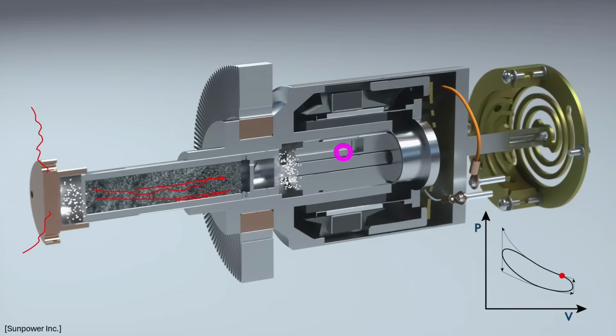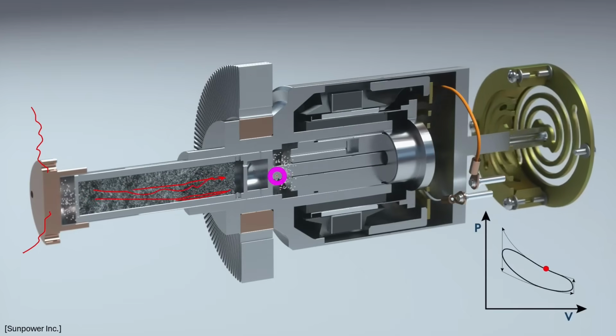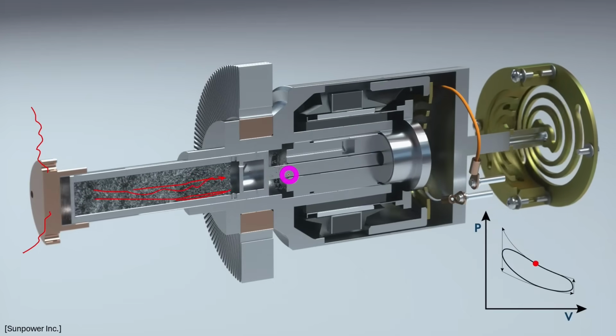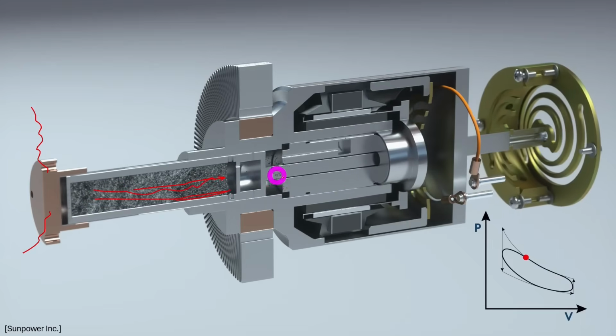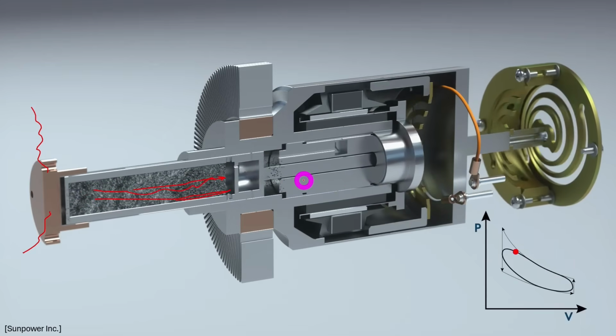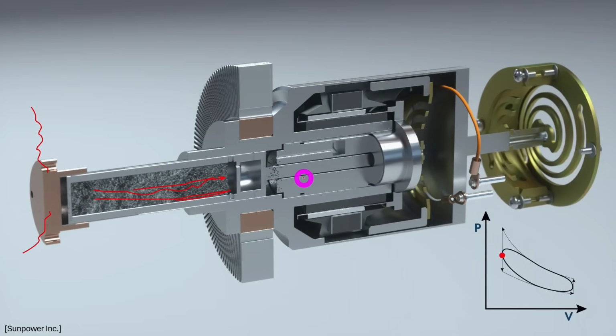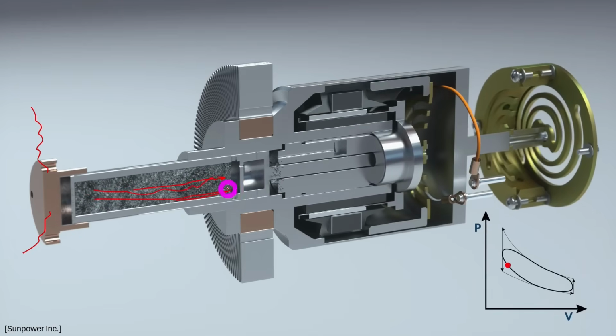Now, the gas that's typically inside of this at very high pressure is helium. They use helium for several reasons. One is, of course, because it's a noble gas, it's inert, it doesn't interact with anything. But also, helium has a very high thermal conductivity compared to some of the other gases. It's, for example, an order of magnitude more conductive than, say, nitrogen is. So helium will help in this situation to be able to remove the heat from it as much as possible.